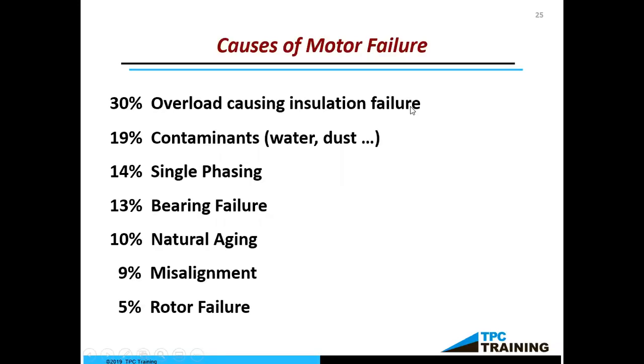If we are vigilant and doing our meg test semi-annually or annually, and that number starts to get down near 5, we could tell the boss, hey, be careful, because, you know, we're getting ready to have a motor go on us. Contaminants are also an issue. So I know in a lot of food processing facilities, we have to hose down and a lot of water everywhere, or our grain facilities, there's dust or whatever. And it's important to try to keep our motors clean.